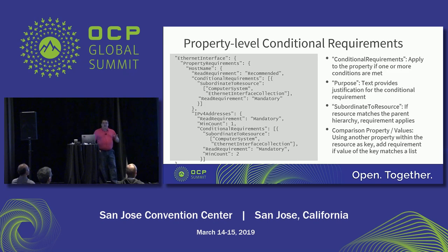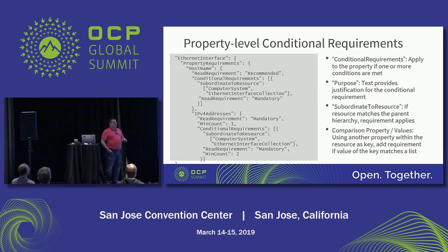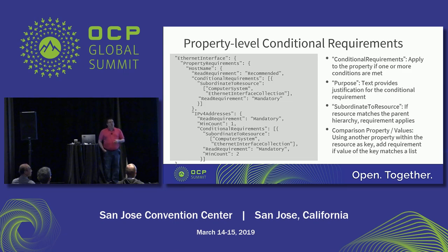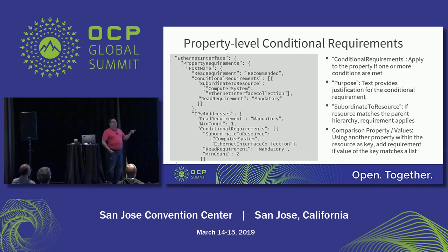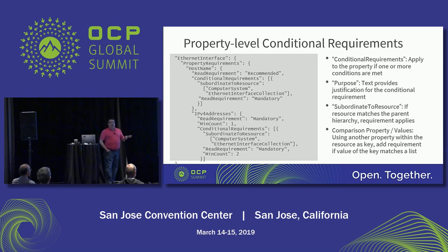The conditional requirements are the most complicated. They're a way to say: if you have this, or if this condition is true, then you have to have these things. This comes into play a lot with what we call "if implemented." I can't require you to have a fan, because if you are a liquid-cooled system you don't have any fans. We wouldn't want a liquid-cooled system to fail the OCP manageability profiles because they don't have fans. We also don't want someone to put a dummy fan object with no readings and fake data just to make the software happy.